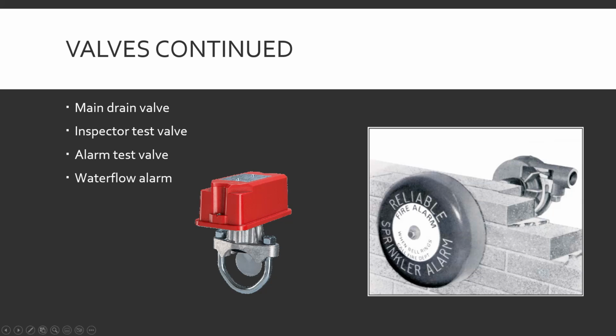And usually, these inspector test valves and the alarm test valves will often dump out outside the building somewhere, so there's not water all over the floor. The alarm test valve is exactly what it sounds like. It's a little valve to let water out of the main system, of the pressure, the actual sprinkler system. So the system, the little controller, the little reader right here, because this is the alarm test valve. Oh no, this is a water flow alarm. Alarm test valve. Short version.